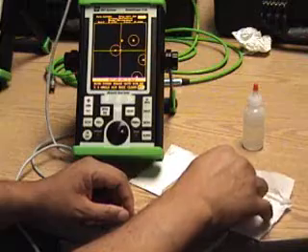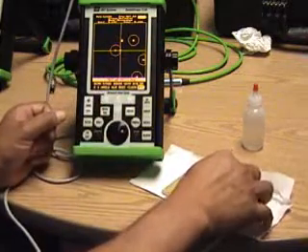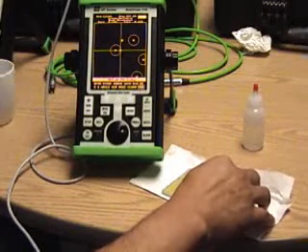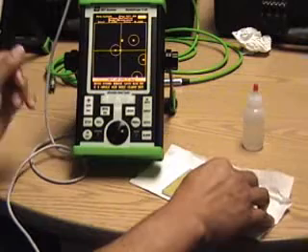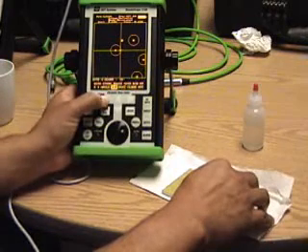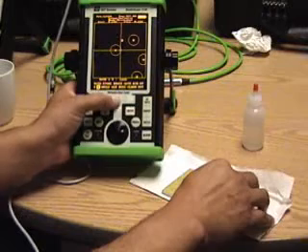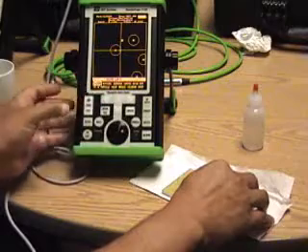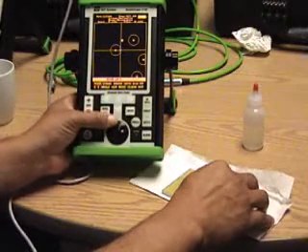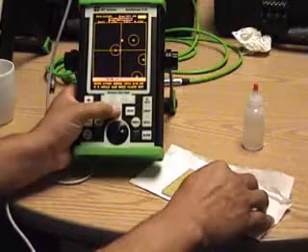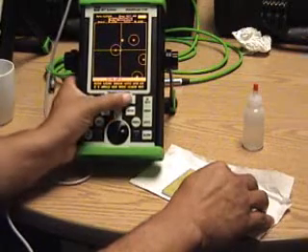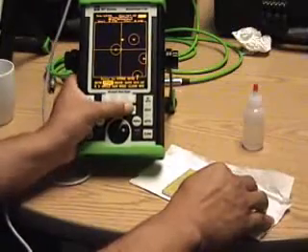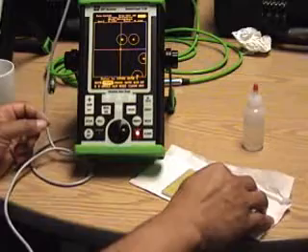I notice that I need to reposition dot position number four into its correct position. Obviously, at the gain setting I had, it didn't have enough sensitivity to pick it up just right. So what I will do is go back to dots using my arrow keys and hit enter. It automatically sequences to dot position five, but I want to change dot position four. I will change it back to dot position four, go to store, hit enter, hit enter again, and that restores my dot position.